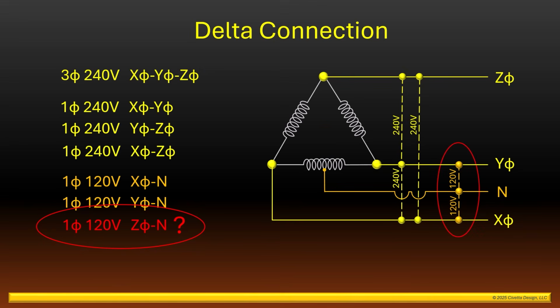For this reason, the Z phase stands alone and has its own nickname. The Z phase is sometimes referred to as the high leg. Some line workers also refer to this as the stinger leg. If you're wondering what voltage potential exists between the high leg and the neutral, let's take a look at that for a moment.